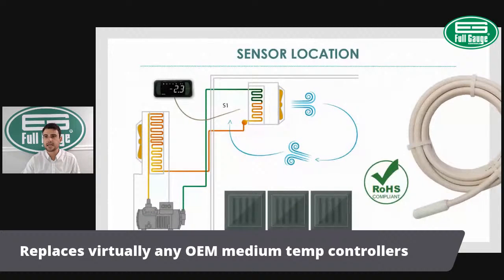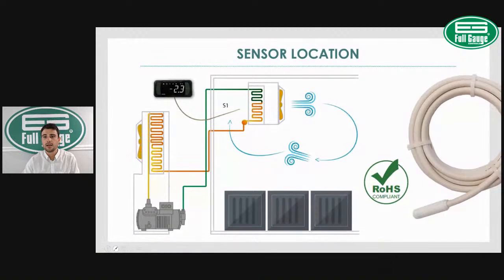So here is a question that I get a lot. Where do I mount the controller sensor? As you can see, the 512 has one relay output and one temperature sensor. The temperature sensor senses the temperature on the air return. That's the ideal position for the temperature sensor, on the air return of your evaporator. Why on the air return? Because that's the warmer spot of your cold chamber. So you want to place the sensor at the warmer spot so you ensure that the temperature is kept within the desired limits. So normally contractors and installers will place the sensor on the air return.